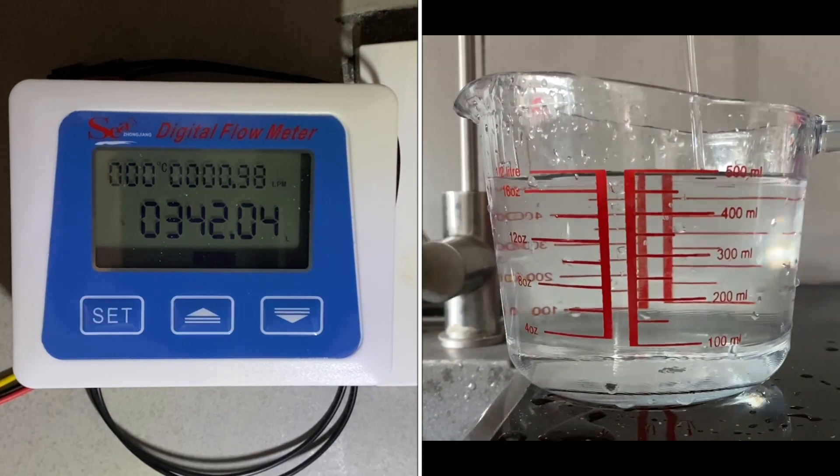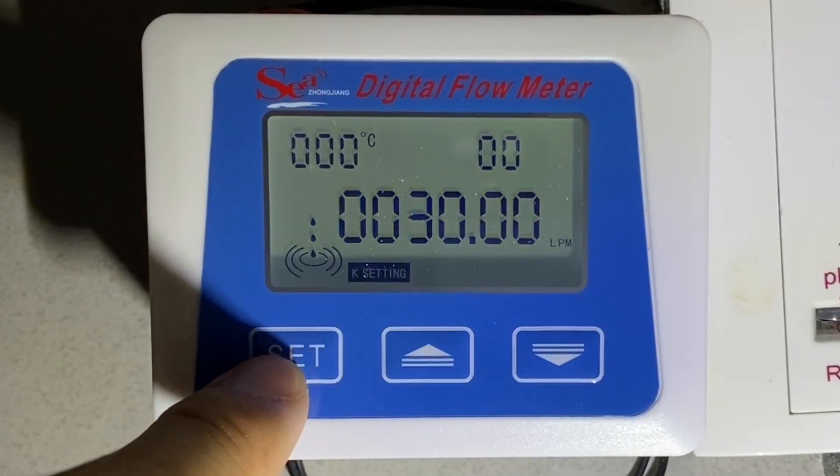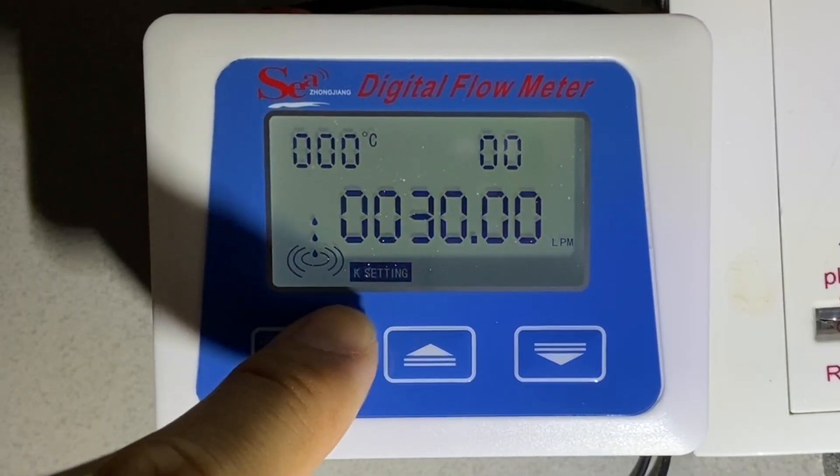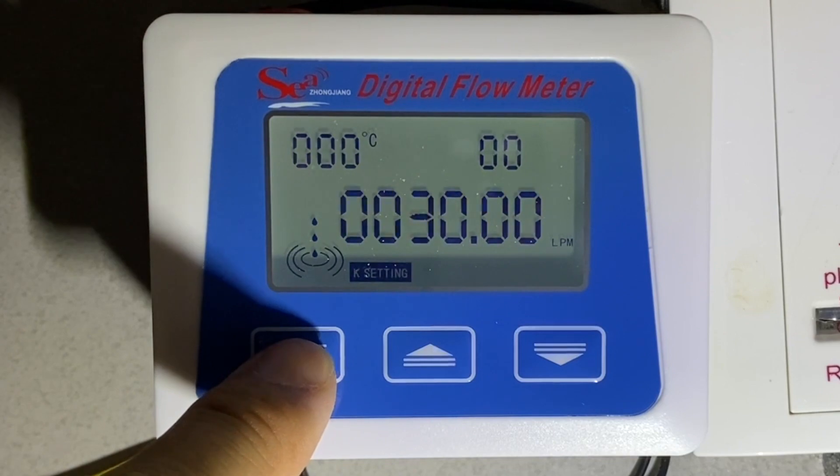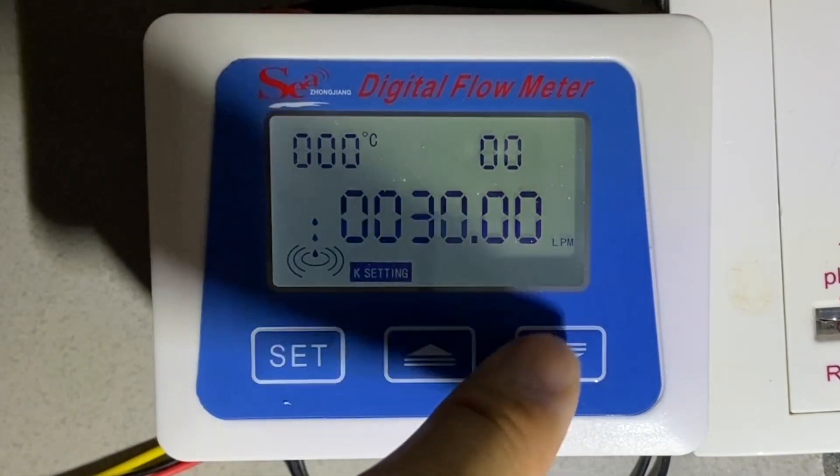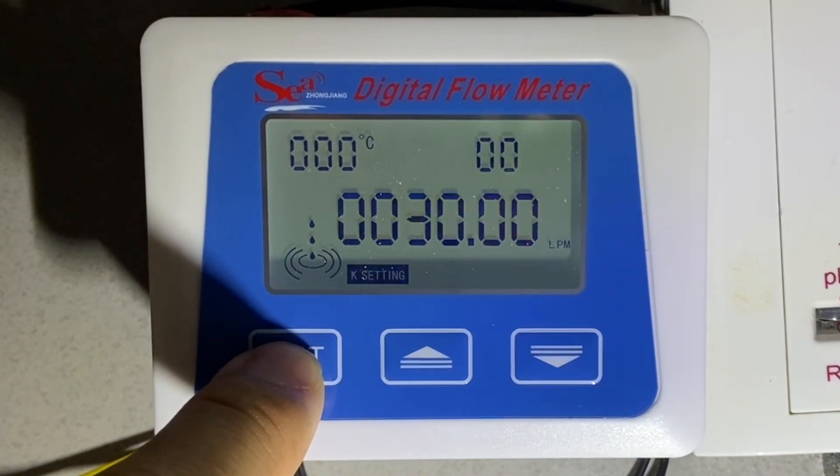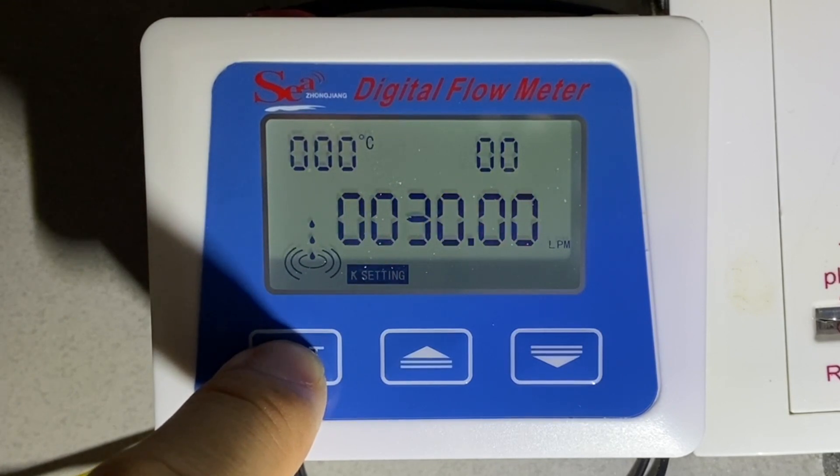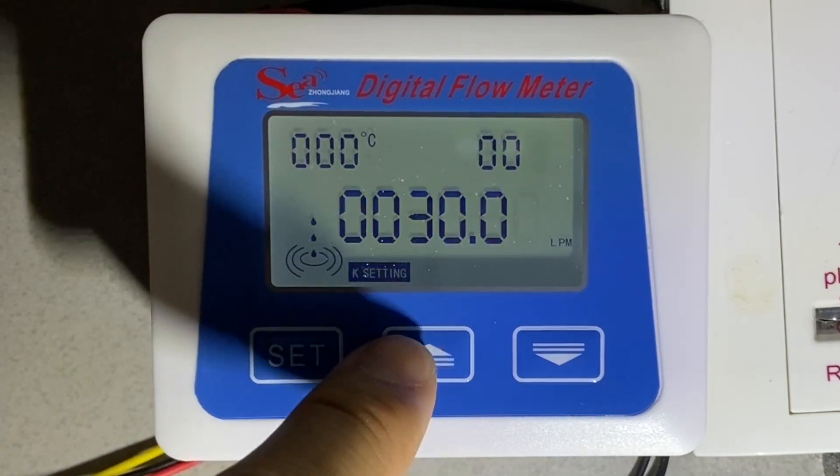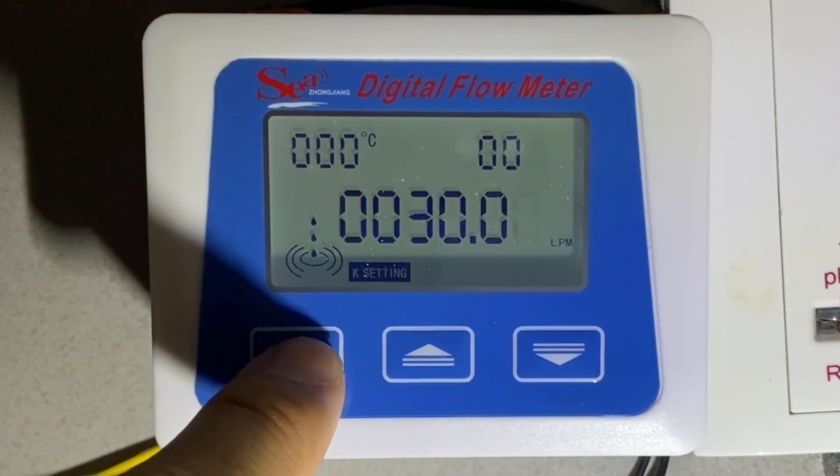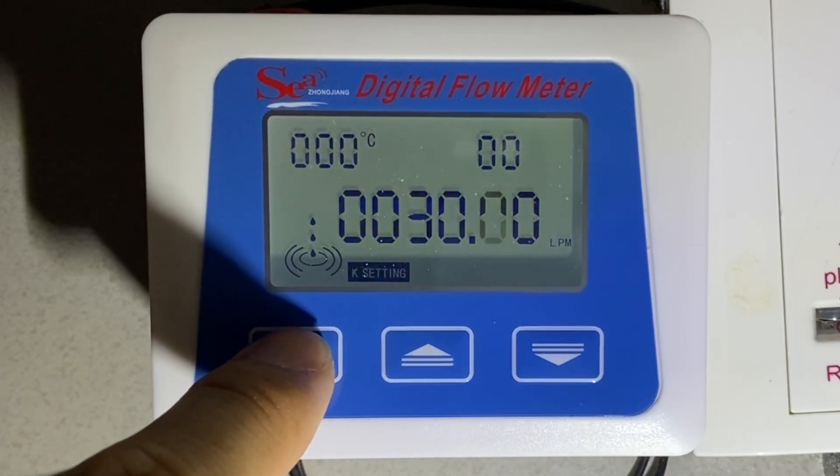Yes, it increased by 0.5 liters. So to do that, you press and hold the SET button, move on to K setting, and then you press and hold the SET button again so that one of the digits will start to blink. Then you press up and down to change the digit, and then you press SET again to move on to the next digit.